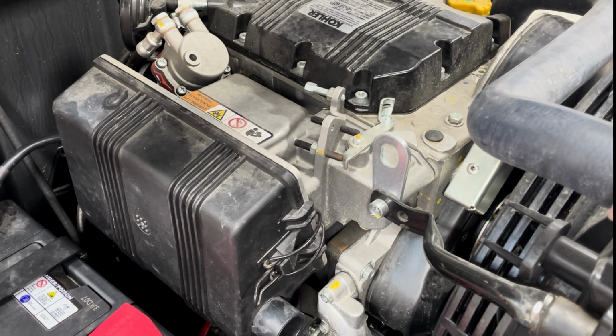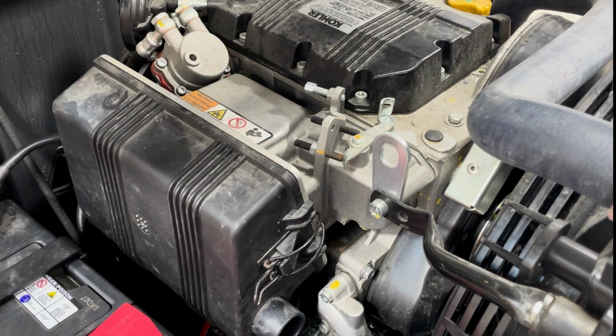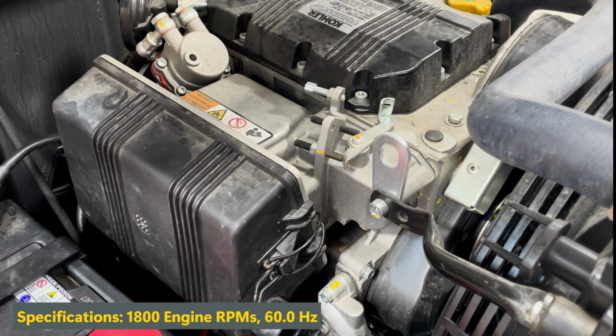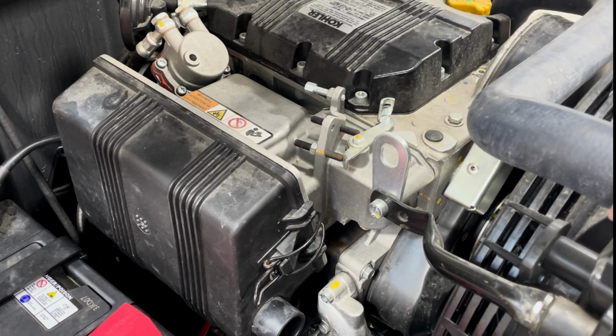In this video, I'm going to demonstrate how to adjust the engine speed on a Wacker Neuson Light Tower if you experience low voltage output out of your generator. Now, the most common reason for low voltage output on a Wacker Neuson Light Tower is more than likely low engine speed. If you have low engine speed, meaning less than 1800 RPMs, you will also experience low hertz, meaning less than 60 hertz of output out of your generator as well.